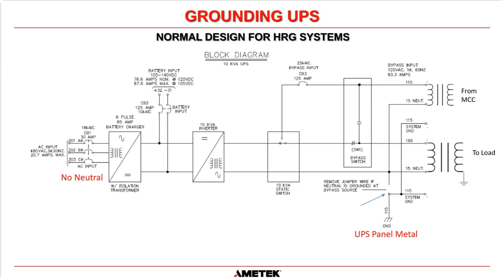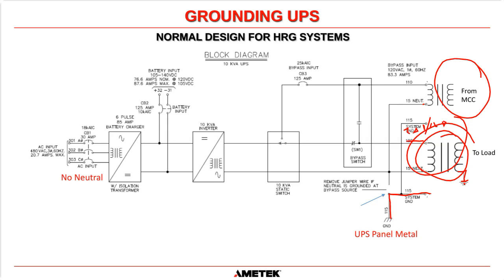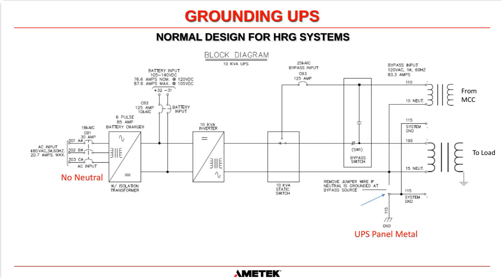We do want to connect the panel ground to the system ground, but our neutrals here are floating. They have no reference to ground whatsoever. The ground is connected on the secondary of this transformer. And what tends to happen is the output of this UPS will be a 208/120, usually on a high resistance ground system. And then it will go feed a big transformer, and then that transformer will then feed an AC panel that feeds the critical load circuits. Okay, but this maintains that the main transformer in the MCC or outside the MCC has no direct connection to ground whatsoever. The only connection to ground is through the high resistance ground circuit.